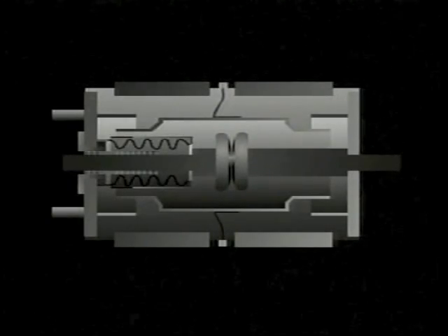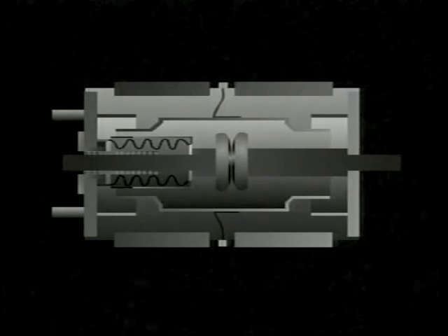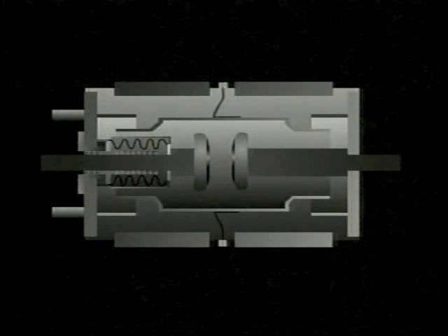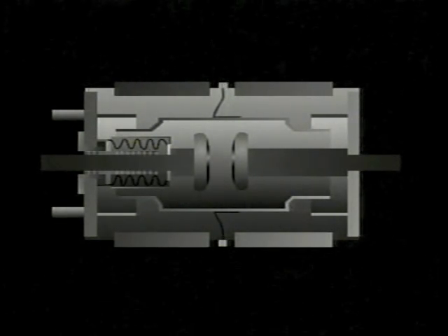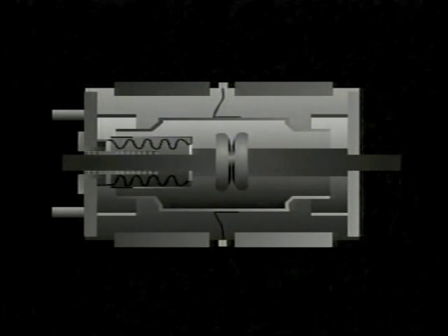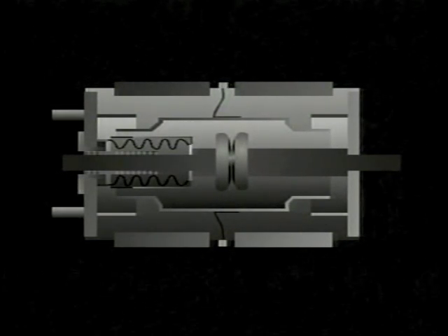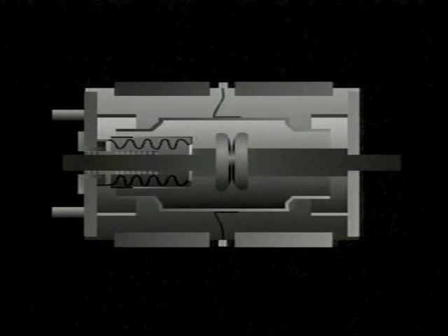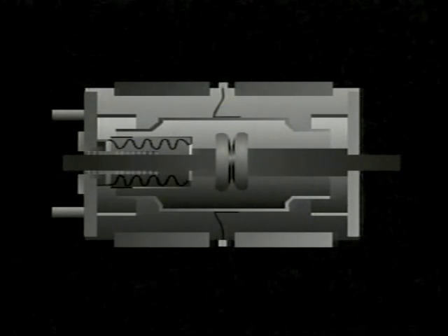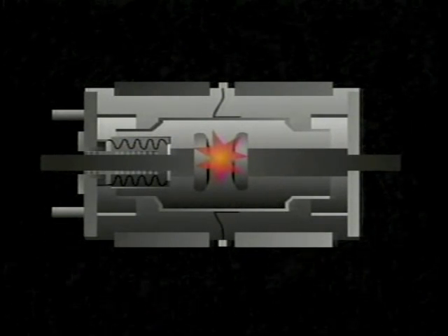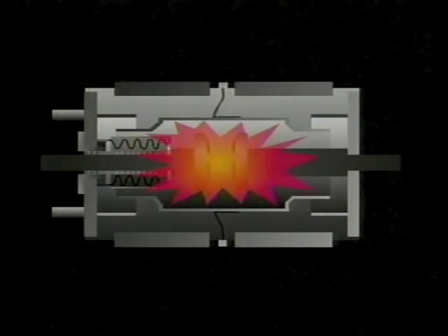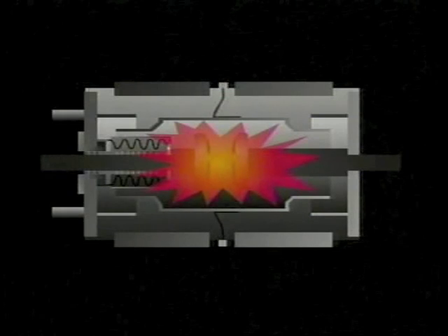A vacuum is an excellent medium for interrupting a flow of current. In vacuum circuit breakers, contacts are drawn apart in a chamber from which air has been removed. When the contacts of a vacuum circuit breaker are closed, current flows through the interrupter. When a trip occurs, the contacts separate very quickly. An arc is drawn between the contact surfaces and is rapidly moved around a slotted electrode surface by a self-induced magnetic effect.